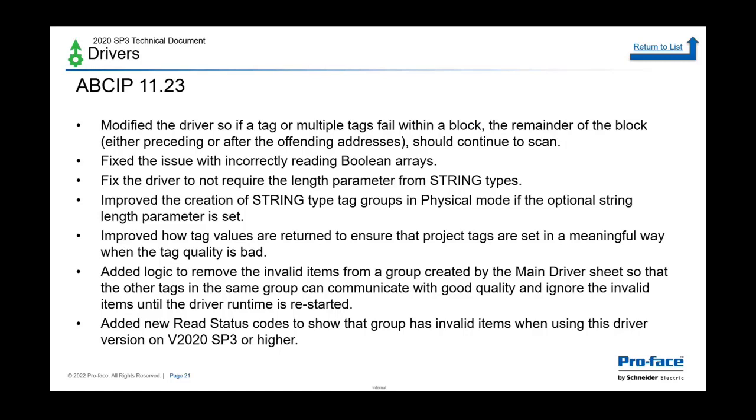It used to be that if any one tag in the block the runtime was asking for failed, the whole block would fail and it would not scan anymore. So they've improved that. If you get one bad tag in the middle of a bunch of good tags, it won't bomb the whole driver. It'll continue to scan. That's kind of huge for Rockwell users. That's been a thorn in the side for some Rockwell users for sure.